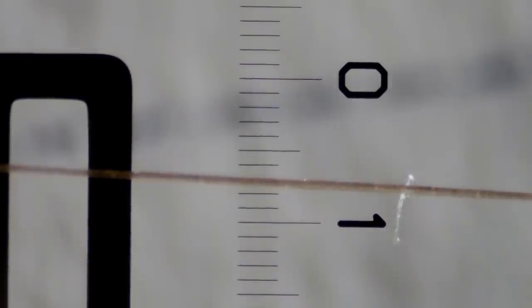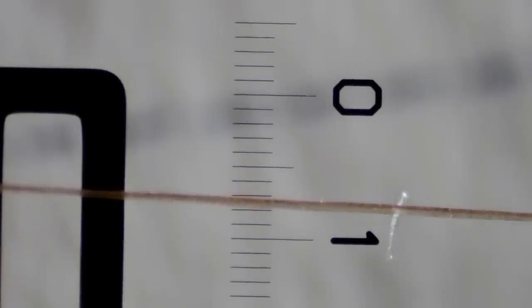There you go. I've got a calibration slide under a microscope — that's one millimetre there. It's probably the easiest metric you can use for calibrating if you don't have a calibration slide: the human hair. There's your typical human hair, which clocks in at just under 100 microns. Those are probably the easiest things to use as benchmarks for this. Generally, you don't actually greatly care about exact size.